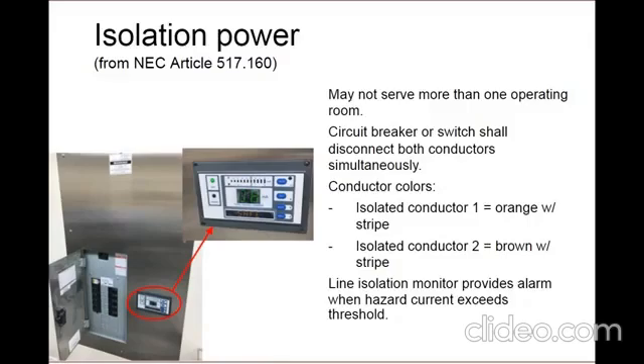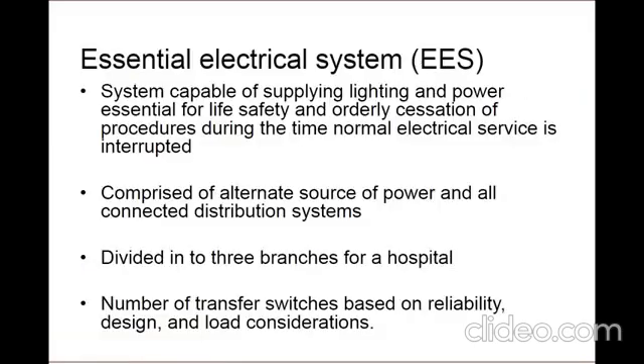The circuit breaker serving the isolated branch circuits must disconnect all conductors simultaneously. This is an ungrounded system, so both conductors serving a single pole circuit must be opened. The conductors are also not permitted to be installed in a raceway system that contains conductors from other systems. In a typical single pole application, one conductor must be identified with orange and at least one distinctive colored stripe other than white, green, or gray along the entire length. The other conductor must be identified with brown with the same requirements for the stripe. Lastly, the isolation monitor measures and displays the total hazard current along with alarm display lights.